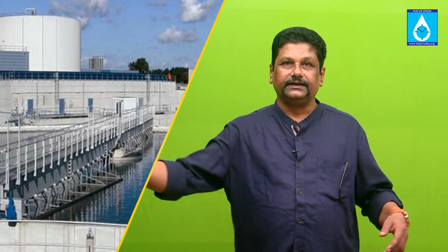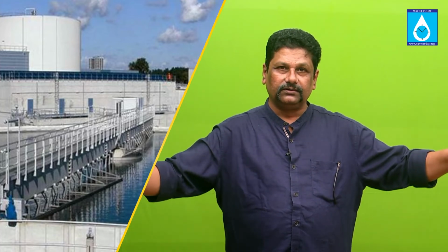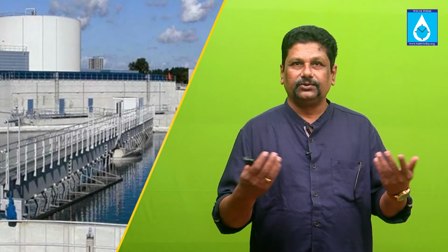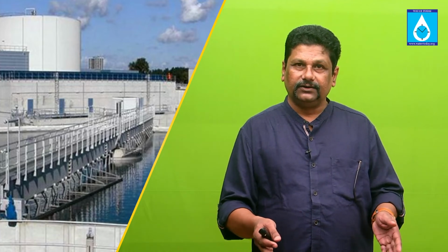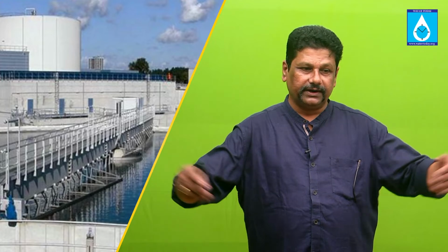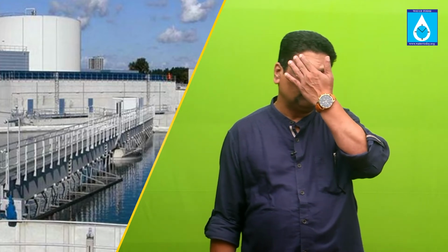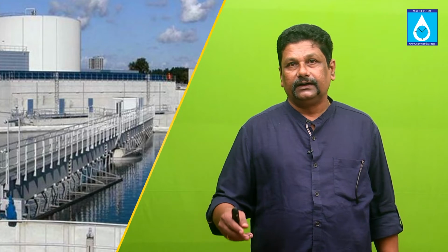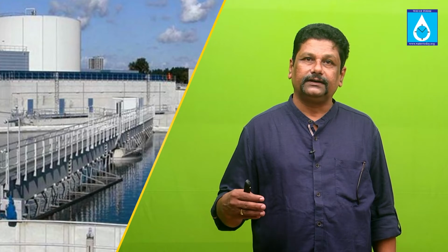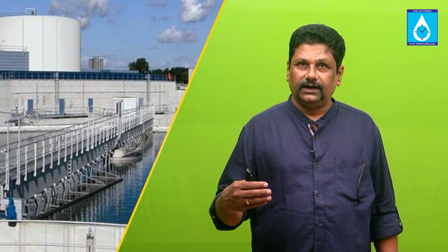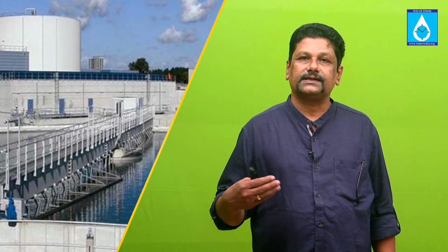After that, on the sides, you need to do some benching to bring all the sewage into the pump for it to pump out. So you can have a larger pit, but you have to maintain all these distances, and also have the benching done so that all the sewage comes into the pump and the pumps can deliver. The most important thing you need to look at is the start and stop level of the pumps. You need to calculate how many starts and stops you can have, so that you give ample time between start and stop.